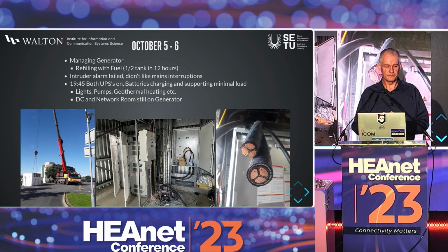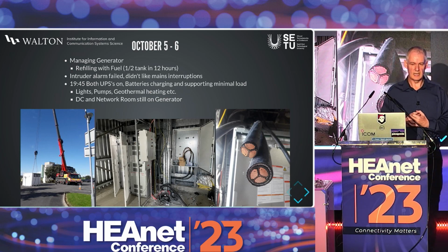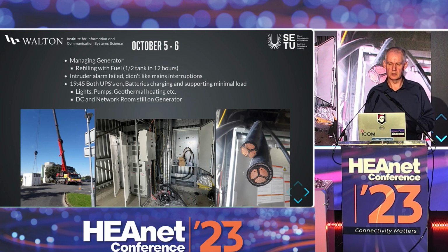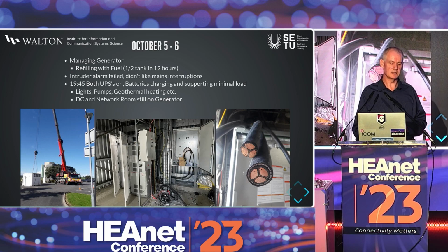By that evening, with the UPSs on again, they wouldn't let us put load on until the batteries got charged. Then we put on minimal load, got lights, pumps, and stuff like that back running, but everything still ran on generator overnight because we still had to recommission and test the generator, fail over it, that type of thing. Would it come back on? They all still had to be tested.